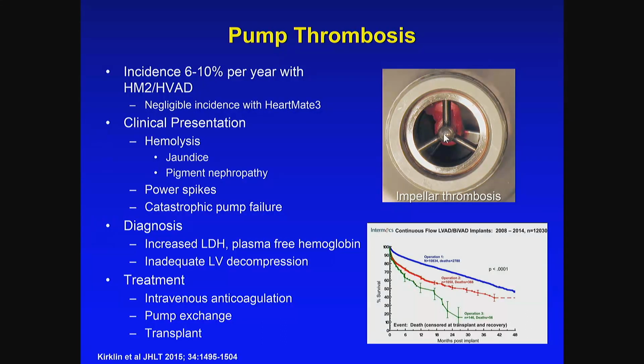There is a clot that has developed on the inflow stator and the rotor that increases the drag as blood moves through the pump. In addition, there's a ruby bearing in here that develops heat as the pump rotor moves. And if clot is on there, that heat is not able to dissipate as cooler blood washes by. And so there is thermal injury to the blood elements in addition to increased shearing. That leads to hemolysis, and a typical pattern of intravascular hemolysis with jaundice, pigment nephropathy, hemoglobinuria. The pump tells you that there's increased power consumption because it takes more power to move the blood with a rotor that's clotted. And there can even be catastrophic pump failure where the pump stops abruptly.